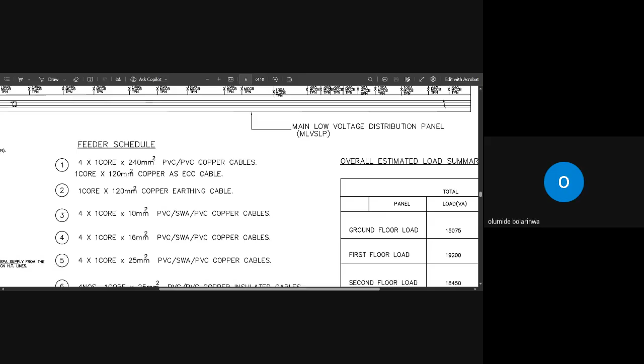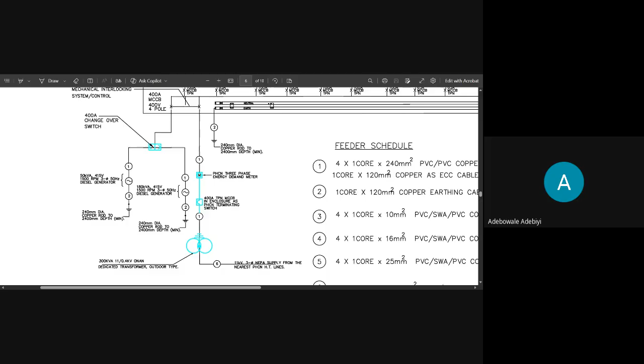Your cable number 2, where is it going to? That's 1 core by 120 mm copper earthing cable. It runs from the earthing to the transformer, and from the earthing to the generator. So it shows that your generator must be earthed, apart from the building being earthed.